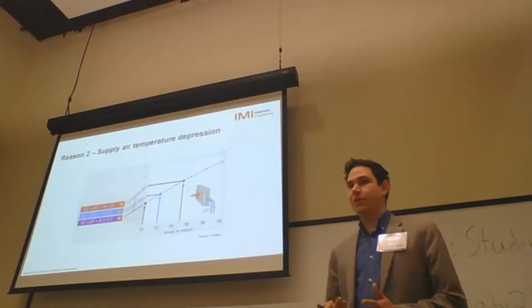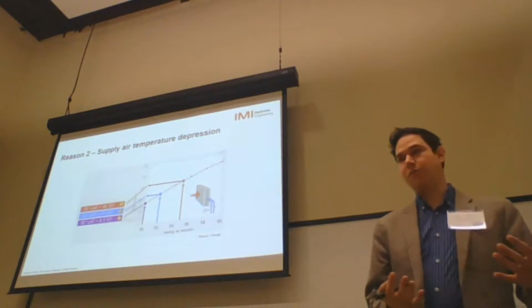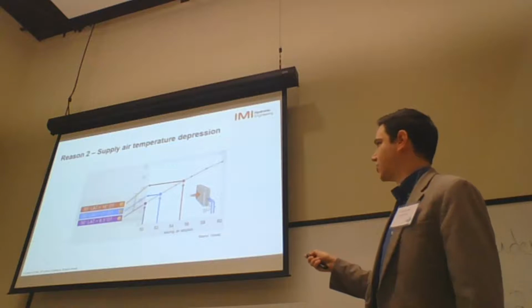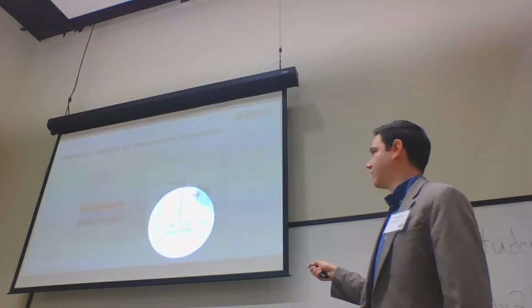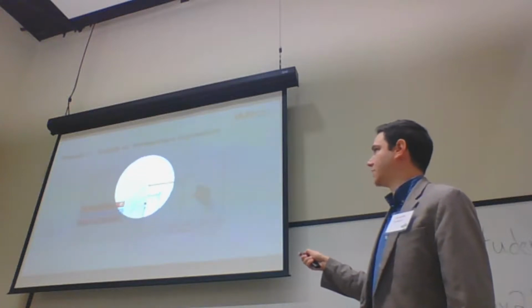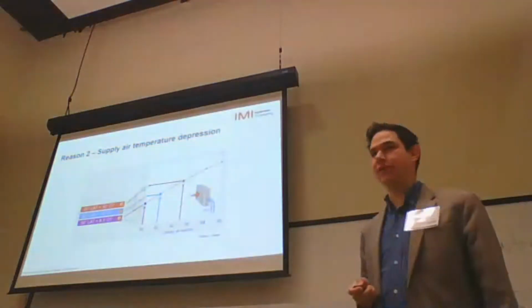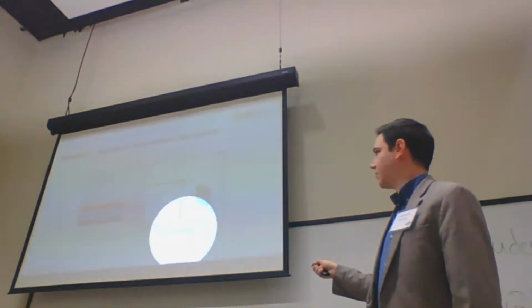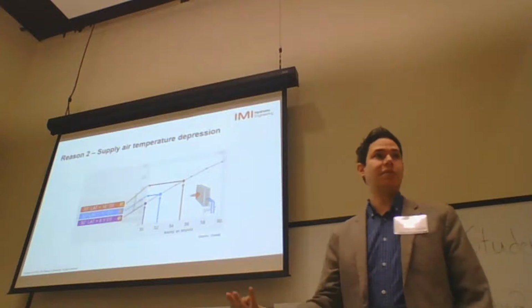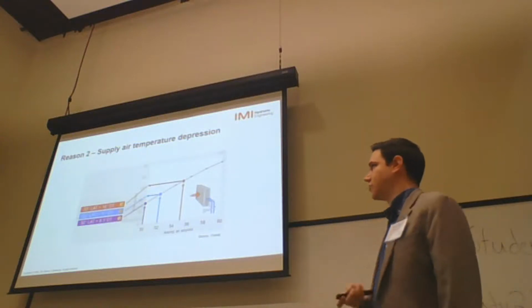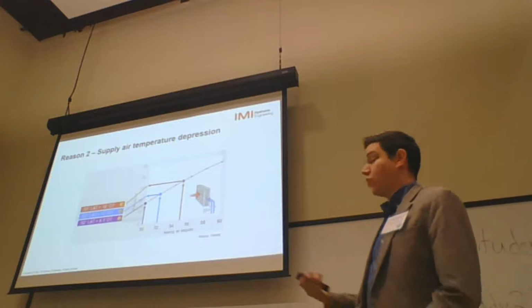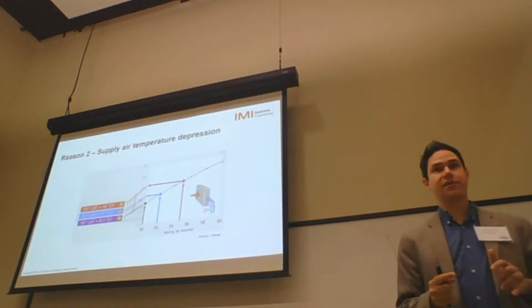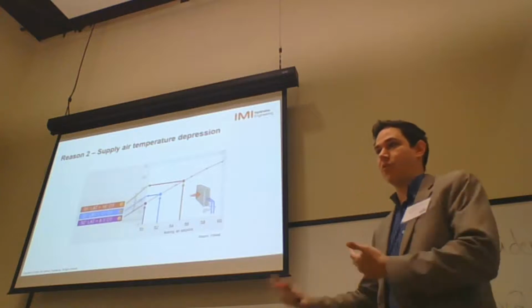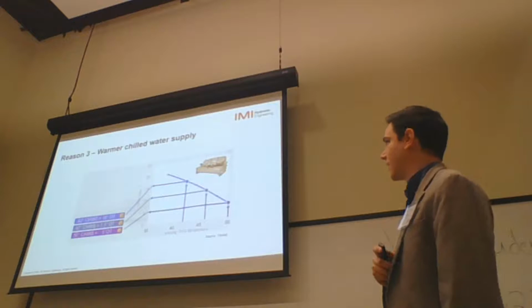Reason number two: this is something that the BMS or the automation guy could change in the system. If you're changing the leaving air set point to a lower number. Let's say the design condition is a 55 degrees leaving air set point, so you're getting the design condition of a 16 degrees chilled water delta T. If somebody changes the leaving air set point from 55 to 50, for example, a lower leaving air set point, you're damaging the chilled water delta T. And in this example, it goes to 8.5. So in this case, do not change that set point in the BMS or the automation. Otherwise, you're sacrificing the chiller's performance.